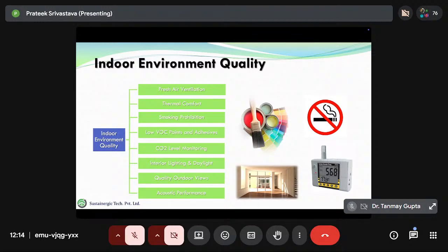When we put in a fresh air ventilation system, it also increases the energy consumption of the building. So we try to put CO2 sensors in the building. Whenever the CO2 ppm levels are higher, the fresh air system should pump in fresh air, and when the CO2 is normal, it should not. So a CO2 sensor feedback system for the ventilation system is important.